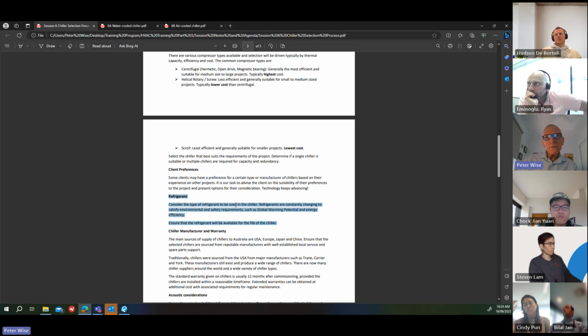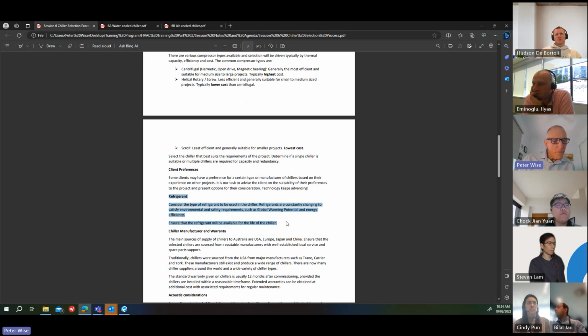Refrigerants. Consider the type of refrigerant proposed for the chiller. The different manufacturers will have their selected refrigerant, generally speaking, which may have a limited life. Some refrigerants are being phased out to satisfy environmental and safety requirements, such as global warming and energy efficiency. So we need to ensure that the refrigerant will be available for the life of the chiller. Now, I'm not going to mention anything specifically, but HCFCs, for instance, will be phased out in the coming years. Maybe by 2030, you'd have to check. But there are new refrigerants being developed all the time. They're looking for better efficiencies. It can affect the size of the machines. The machines may get bigger to accommodate a different refrigerant. So all those things need to be looked at.